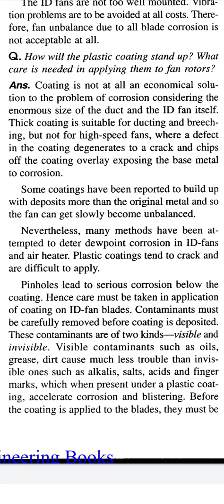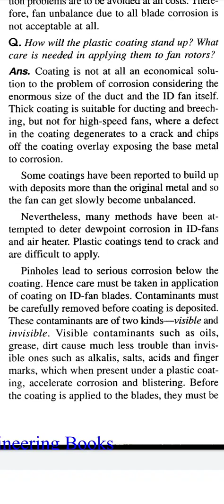Nevertheless, many methods have been attempted to deter dew point corrosion in ID fans and air heaters. Plastic coatings tend to crack and are difficult to apply. Pinholes lead to serious corrosion below the coating. Hence, care must be taken in application of coating on ID fan blades. Contaminants must be carefully removed before coating is deposited.